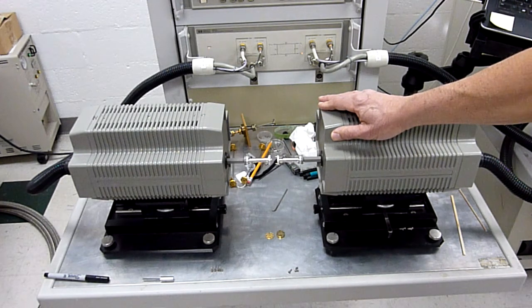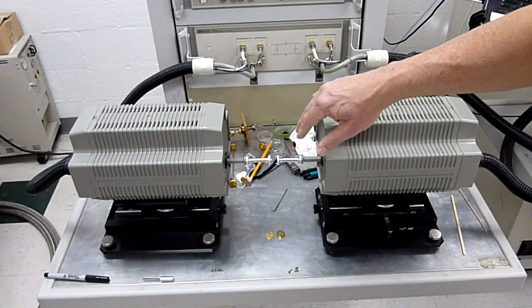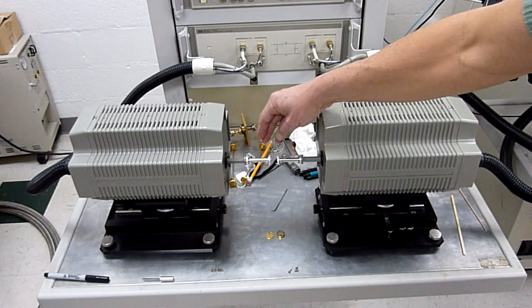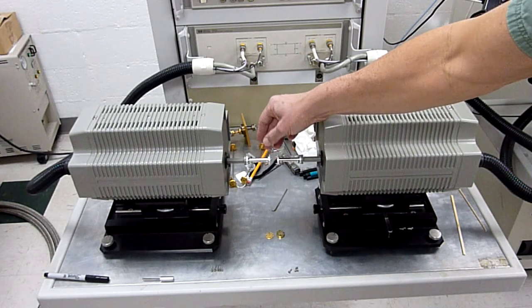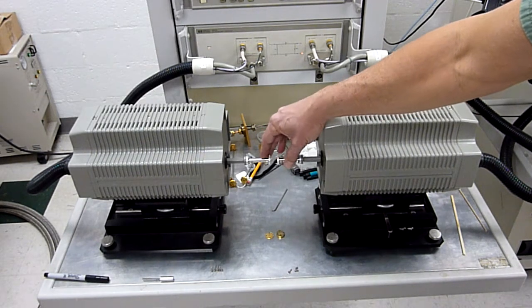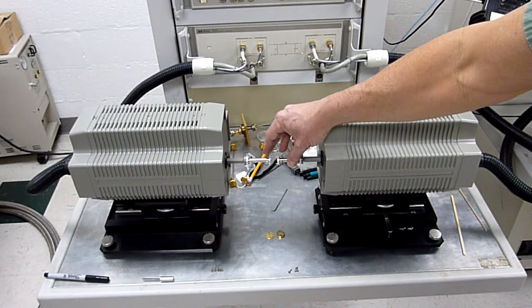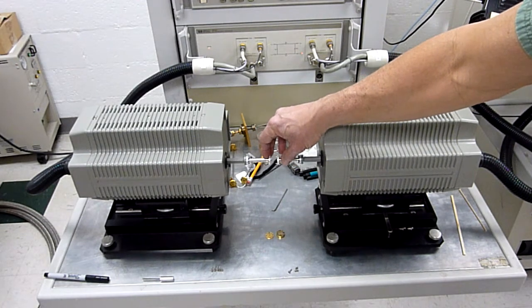But there were actually little shards of metal projecting into the waveguide aperture. You actually had some distortion of the waveguide itself, so you no longer had a good rectangular waveguide opening at these ends of the waveguide.